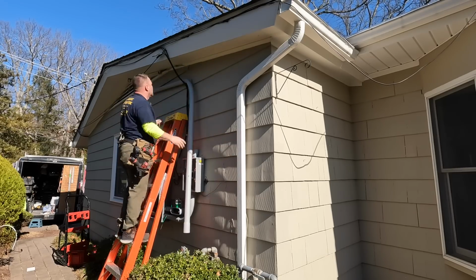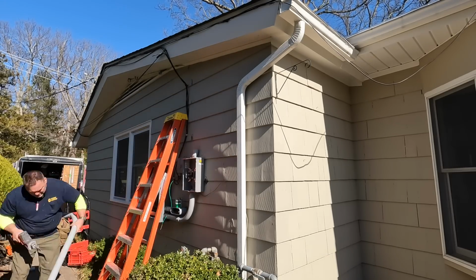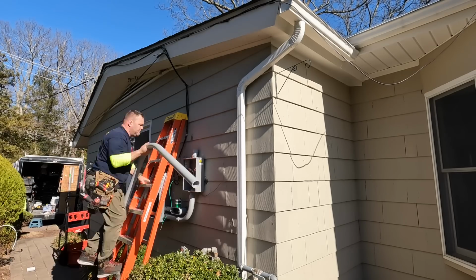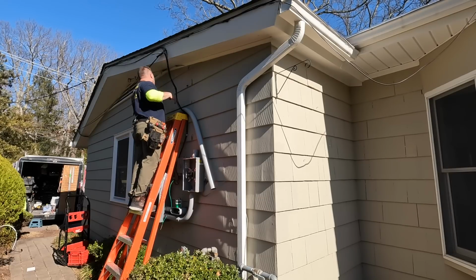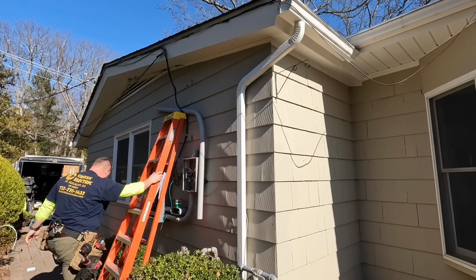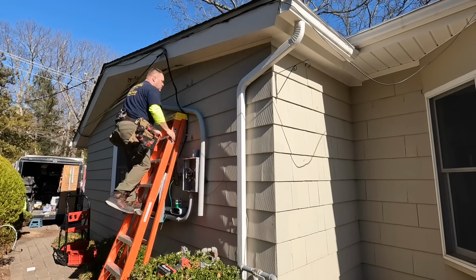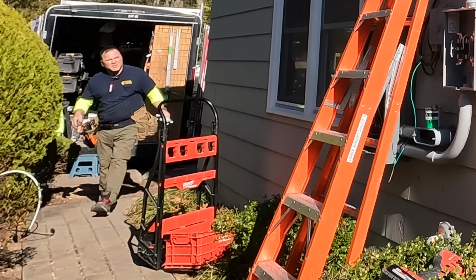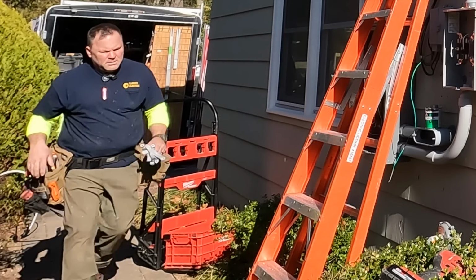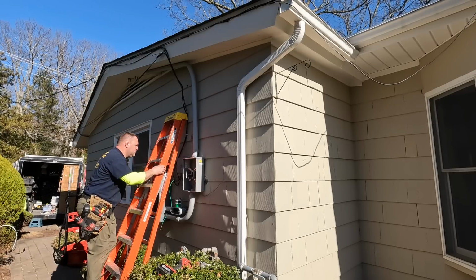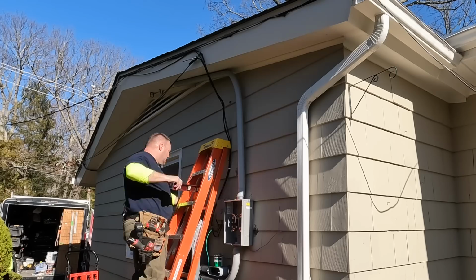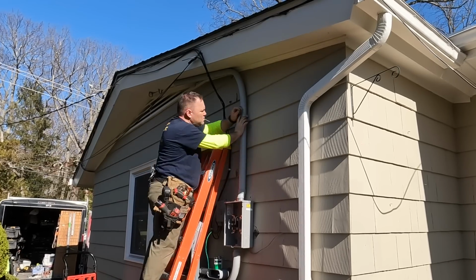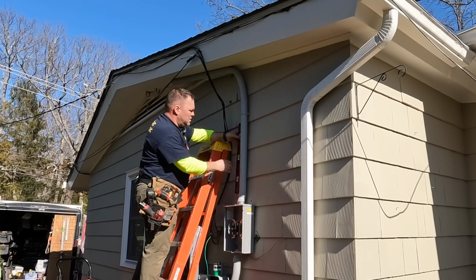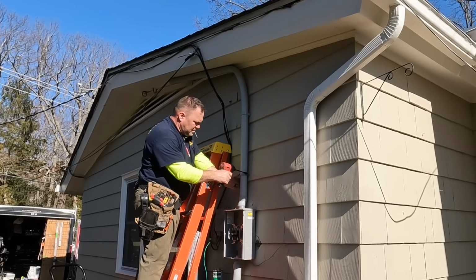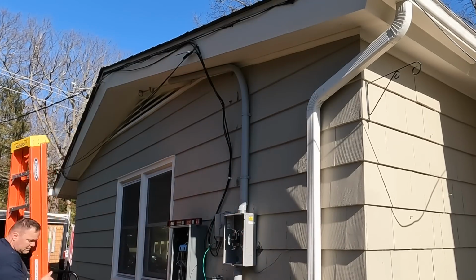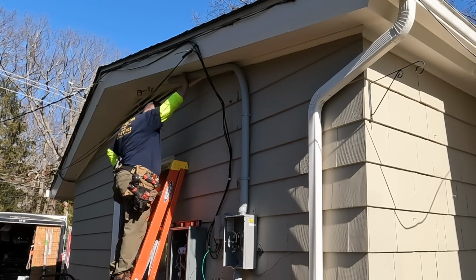All right, so here, this is the piece of PVC that I bent the first thing in the morning, just so I can get that right angle at the top of that soffit right there. It's very close to not being 10 feet high for the bottom of my drip loop. I think it's about 13 feet or maybe 12 feet to the top of that pitch right there. But as you can see, the existing service drop was there from before, and I did measure the drip loop from the previous installation, and it was not 10 feet. So I made sure I went up a few more inches to the exact top, as high as I could go, and then my drip loop was absolutely higher than 10 feet from the ground, which is a National Electric Code section that must be adhered to for service upgrades.